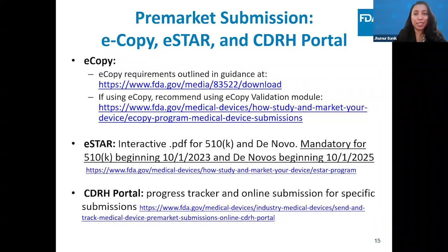So for your actual pre-submission content, there's a table of contents, which is important, page numbers, and making sure it's divided by review area. So a specific section for administrative documents, bench testing, animal testing, clinical testing, etc. Any prior regulatory history concerning this device. So all pre-sub interactions, IDEs, and communication in history in between these submissions are very helpful also, because though the FDA review team will be familiar with it from a historical standpoint, there could be shifts in lead reviewers and whatnot. It happens, especially with the length of time from Q-sub, pre-sub before an IDE to that point.